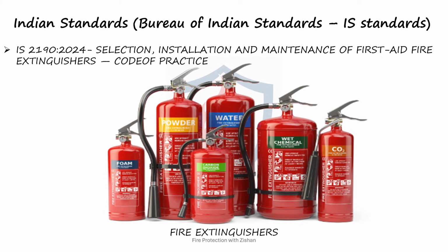IS 2190:2024 specifies the requirements for extinguisher selection based on the type of hazard, as well as guidelines for location, mounting height, accessibility, inspection, and routine maintenance. The standard also emphasizes regular checks to ensure that extinguishers remain fully charged, operational, and ready for use during an emergency. In simple terms, a fire extinguisher can often stop a small fire before it becomes a major incident.